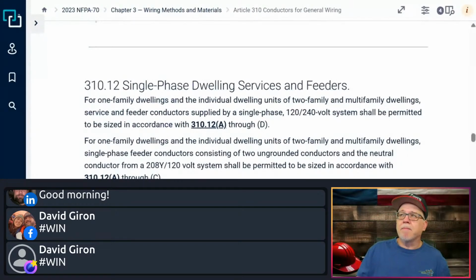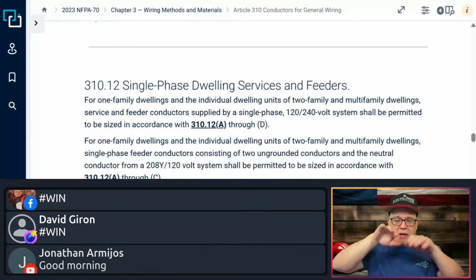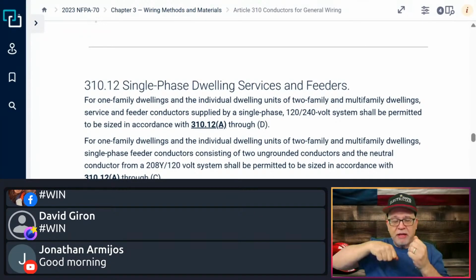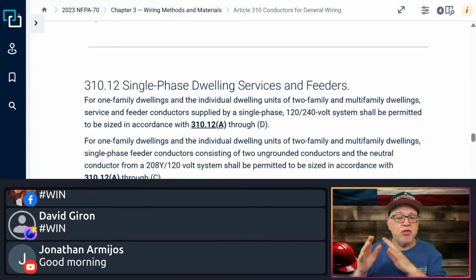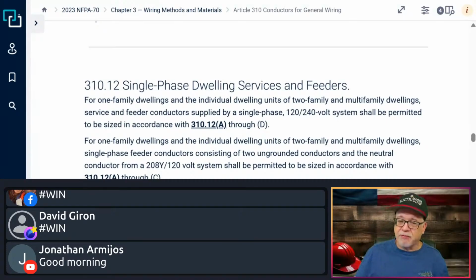So could you full size it? Absolutely. Can you buy cables with the grounded conductor full sized? Absolutely, you can. But typically an SEU, okay, with the 2 conductors and the helical grounded conductor, the helical wrap around it, it's kind of gray and it looks like a U when you turn it on the side. That's a type U. Typically that helical that you make up yourself, that's only going to be equivalent to about a 2/0. And it should be fine for most applications, but you still need to do a load calc, okay?